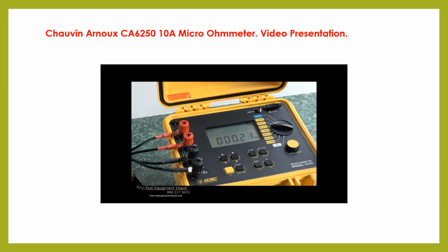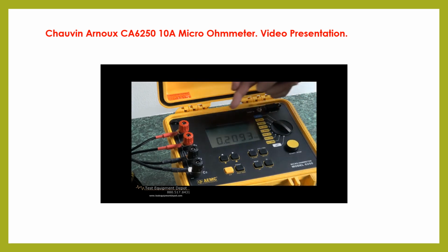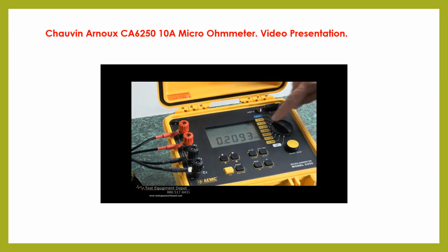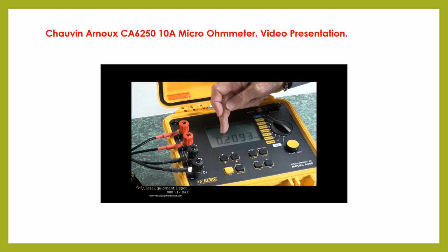But we still have some further sensitivity we can test, and we can run it up to 10 amps, but at 25 milliohm scale. So we just increase sensitivity by a magnitude of 10. We're still at 21, and let's finally run 10 amps through it and read it. Aha! We are reading 0.2093 milliohms, which effectively is 209 microohms, and it's 209.3 microohms.